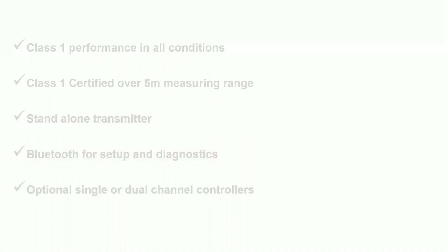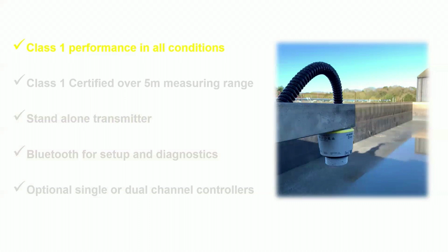So first one I want to talk about is the Class 1 performance in all conditions. Many level and flow applications are subjected to environmental conditions which can change quickly and be quite unpredictable, typically during storm events when accurate and actionable data is at its most valuable. So by having a system installed that is very resilient to these different harsh measuring conditions, it allows you to make decisive actions. It gives much cleaner level and flow data. So it's much better data to be able to analyze for planning and for modeling. And as Peter was talking about before, we're really reliable and accurate without the need of protecting it from direct or indirect sunlight. We don't have any issues with things like condensation and build up around the sensor. So much less maintenance and a really stable signal. Simpler installations, as I was saying before, and helping people to save time and money.